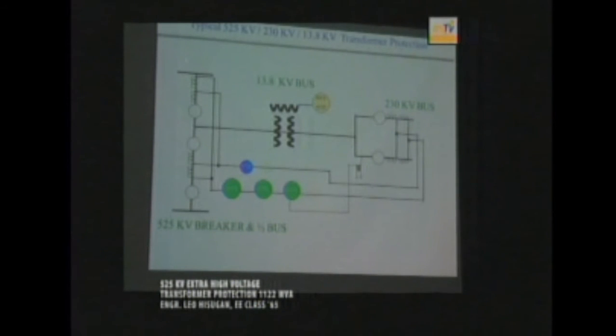So this scheme here is a breaker and a half scheme, and here we have a double bus single breaker scheme. So on a breaker and a half bus configuration, this is your bus number 1, for example, and this is your bus number 2. If this is my 525 kV transformer, I'm using one main breaker for this transformer, and half of this is being utilized by this transformer. The other half is being utilized here if it has another line here. The low side of the 230 kV bus normally has 2 circuit breakers. One for maintenance, and one is being used all the time.